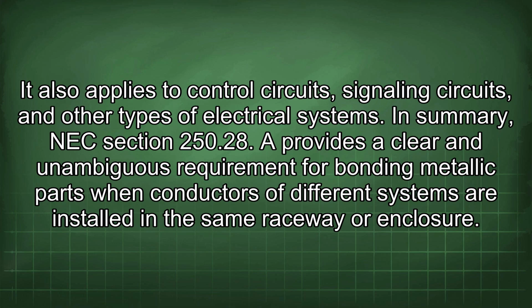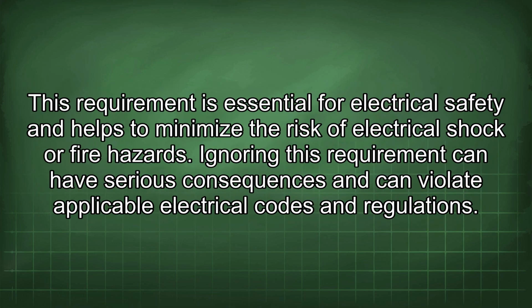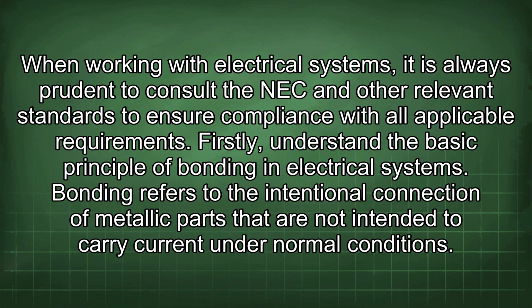In summary, NEC Section 250.28 provides a clear and unambiguous requirement for bonding metallic parts when conductors of different systems are installed in the same raceway or enclosure. This requirement is essential for electrical safety and helps to minimize the risk of electrical shock or fire hazards. Ignoring this requirement can have serious consequences and can violate applicable electrical codes and regulations.